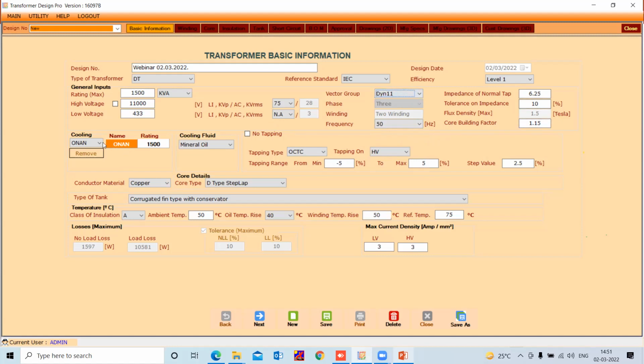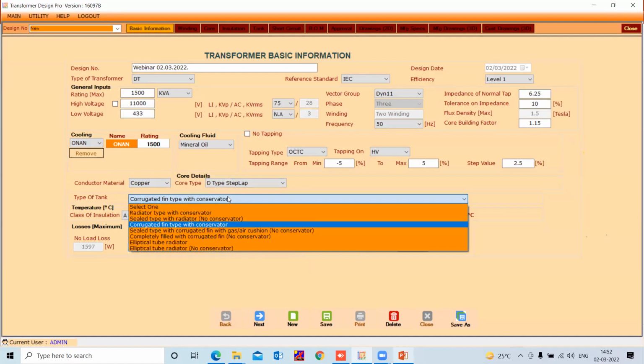You have chosen the cooling. Various options are there: dry type, oil cooled, and also ester. You have chosen ONAN with mineral oil. And then the tapping, you have chosen OCTC, that is off circuit tap changer, on the HV side with a range of -5 to +5, with a step value of 2.5%. That makes 7 taps overall. Conductor material is copper, and the core type has been D-type step lap. You can select other ones also. Among the various tank types available, we chose corrugated fin type with conservator.